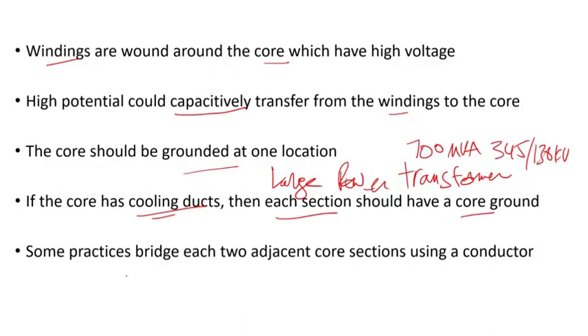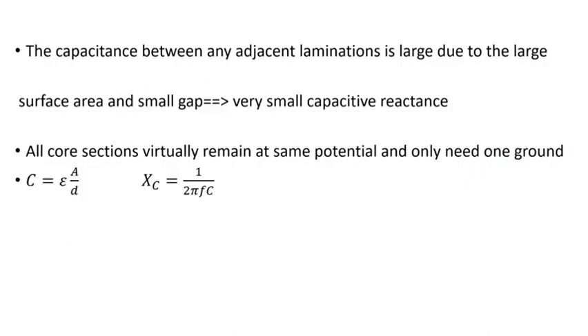However, in some practices they will bridge two adjacent core sections. Basically, you have two core sections with cooling ducts in between them, and they also bridge the two sections, putting some kind of jumper across the two sections. Each manufacturer does it their own way. The capacitance between any adjacent laminations is large, and so is the surface area. So basically, what you end up with is a very small capacitive reactance.